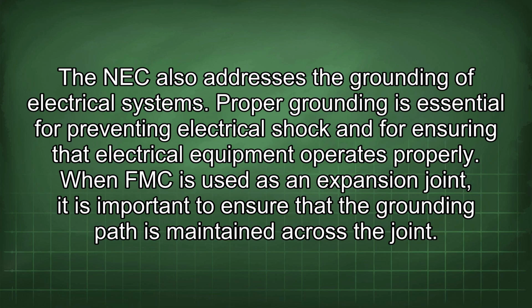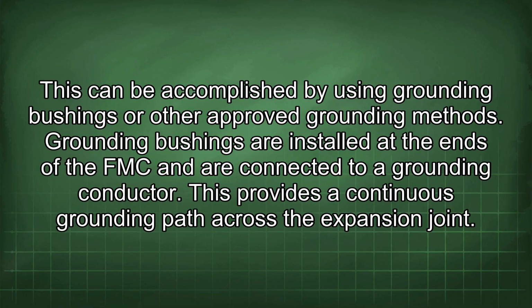The NEC also addresses the grounding of electrical systems. Proper grounding is essential for preventing electrical shock and for ensuring that electrical equipment operates properly. When FMC is used as an expansion joint, it is important to ensure that the grounding path is maintained across the joint. This can be accomplished by using grounding bushings or other approved grounding methods. Grounding bushings are installed at the ends of the FMC and are connected to a grounding conductor. This provides a continuous grounding path across the expansion joint.